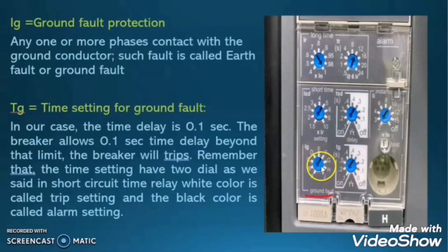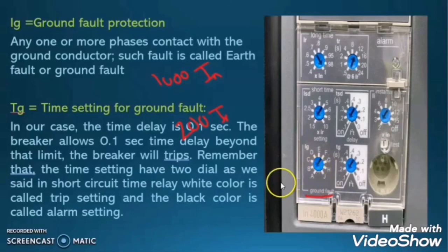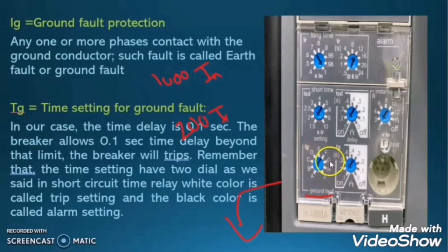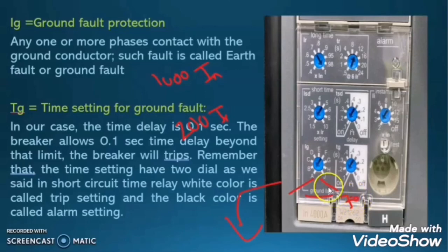If the dial is set on A, this circuit breaker will trip when 20% of the nominal current is flowing into the ground. In our case with 1000A nominal current, A corresponds to 20% × 1000 = 200A. When 200A flows to ground, the breaker trips. Similarly, positions B through J correspond to different values, ranging from 20% to a maximum of 70% of the nominal current.